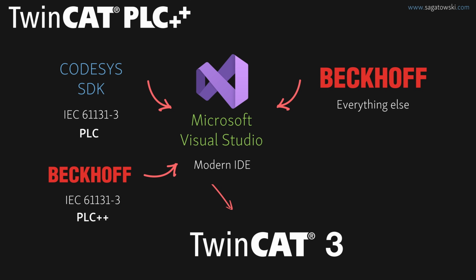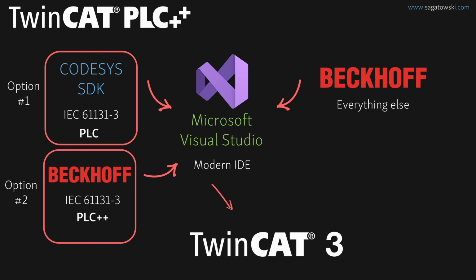Note that this is a pure IEC 61131-3 compiler and not a C++ compiler, as some of the initial guesses suggested. It's 100% purely an editor and compiler for the IEC languages, in other words, structured text, function block diagrams, ladder, and sequential function charts. You'll still be able to use the conventional CODESYS compiler and editor in parallel with the new PLC++, and you can even use them at the same time, as I will show in the live demo.